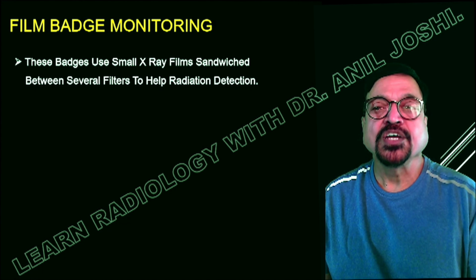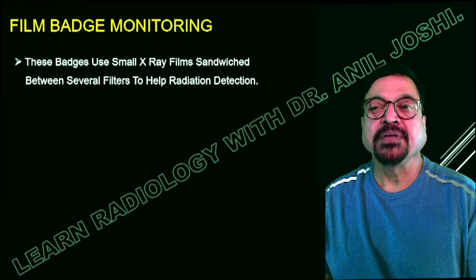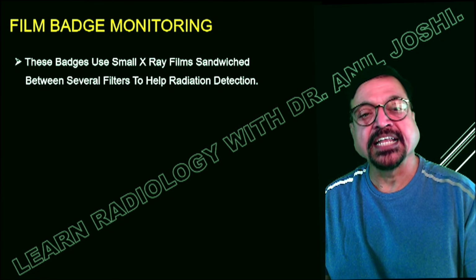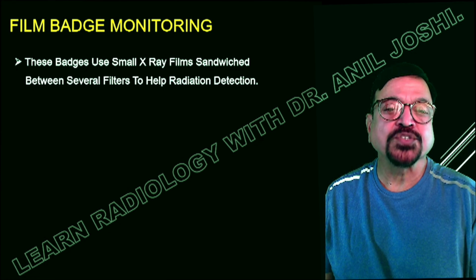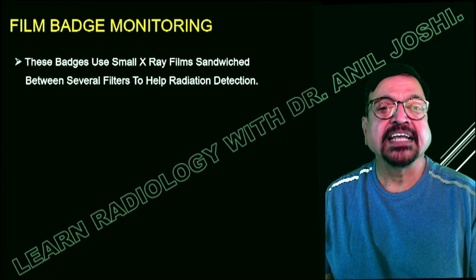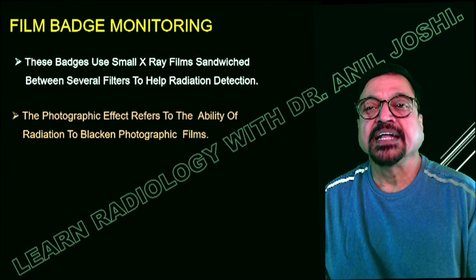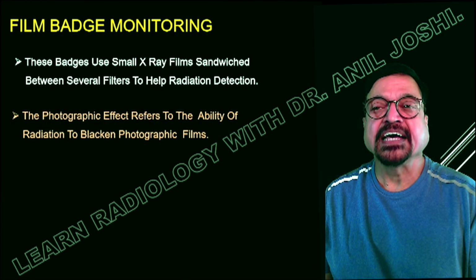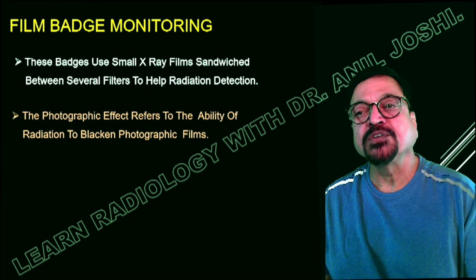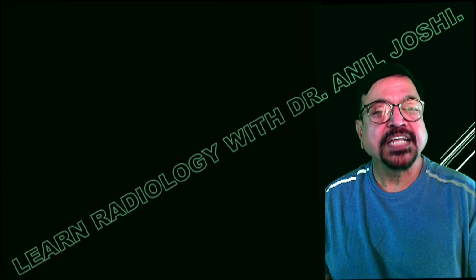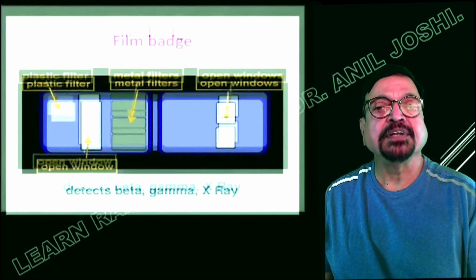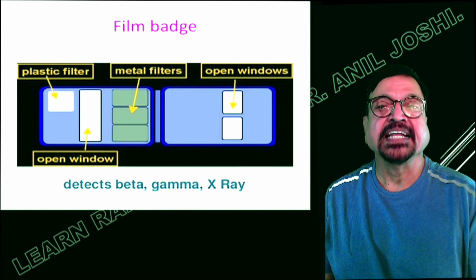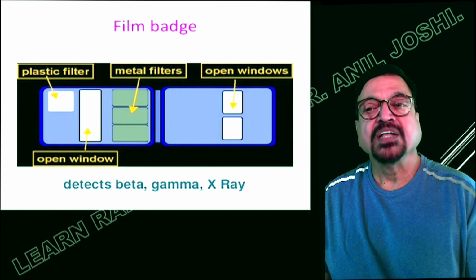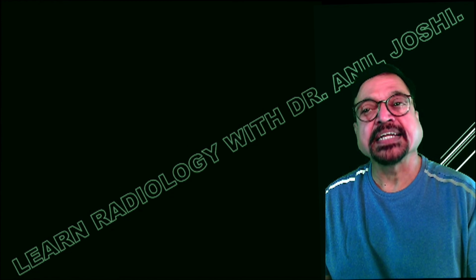The film badge uses a small X-ray film sandwiched between several filters to help radiation detection. When we were radiation students in the 80s, from 81 to 85, we were using these film badges. The photographic effect refers to the ability of radiation to blacken the photographic film. These photographic films were sandwiched between multiple filters, as you are seeing here. There are different metallic filters which were used to differentiate between types of radiation.